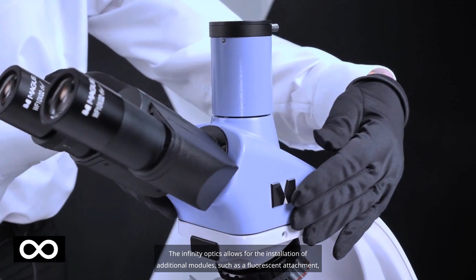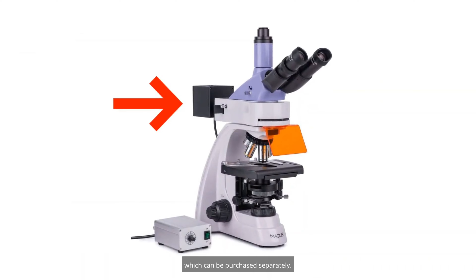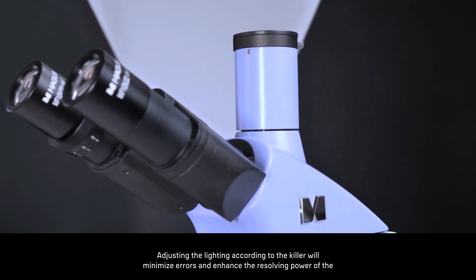The Infinity Optics allows for the installation of additional modules, such as a fluorescent attachment, which can be purchased separately. Adjusting the lighting according to Köhler will minimize errors and enhance the resolving power of the lenses. This results in an accurate image with detail at the limit of resolution for each lens. The field of view of 18 mm or 22 mm creates comfortable conditions for observation.